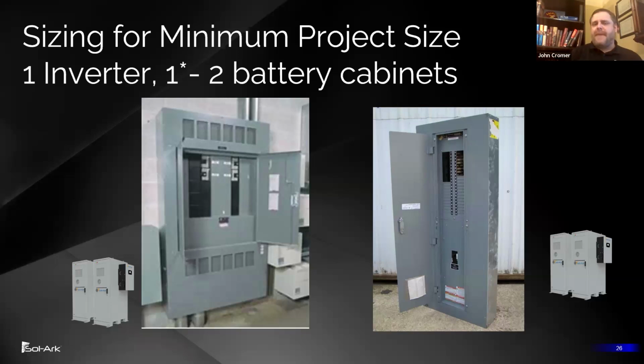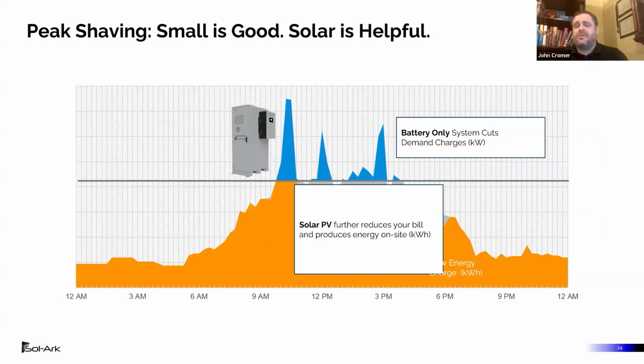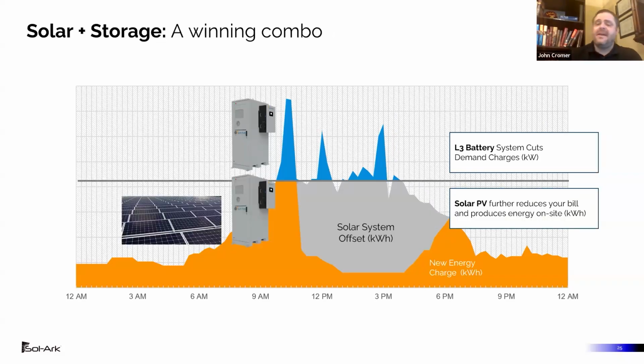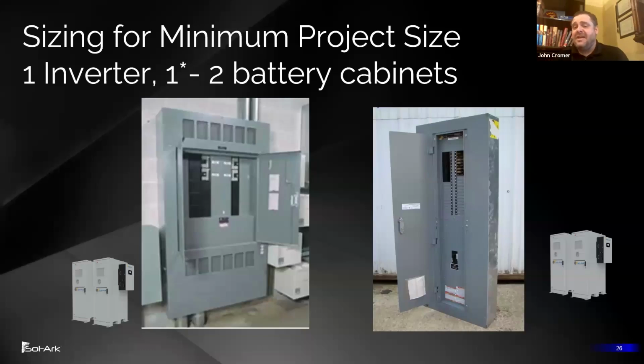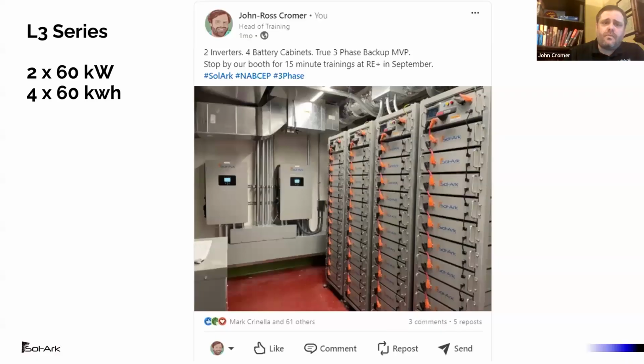So it's just like essential backup in residential, where you offset a sub panel, but you provide energy services to the entire building. Now we're in commercial, and that same philosophy has scaled up to commercial, where you can back up a portion of the building, but provide energy services to the entirety of the building. And when you start looking at the Sol-Ark product line, most of our systems are 1 to 2 inverters and 1 to 4 battery cabinets, and that can be a load side connection. It does not have to be a whole building backup system. And so here are some project photos. This is 4 battery cabinets and 2 inverters.